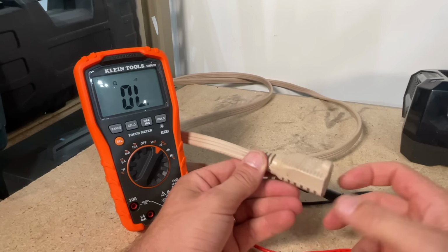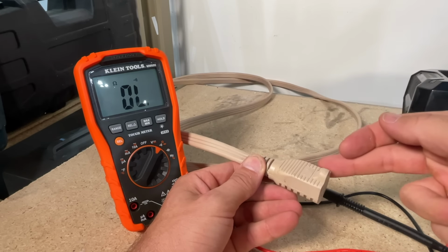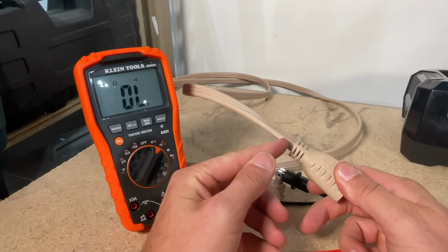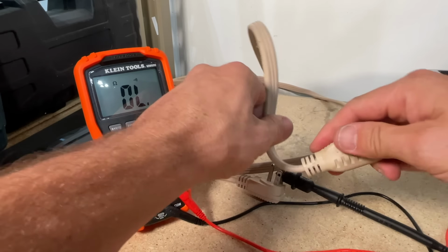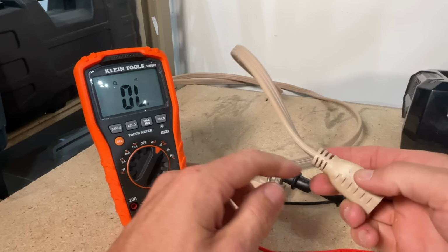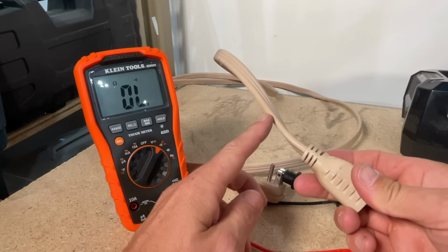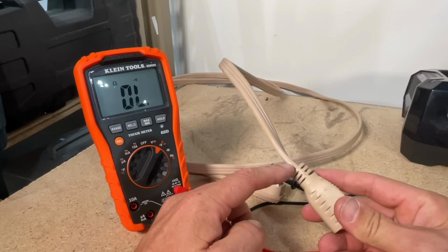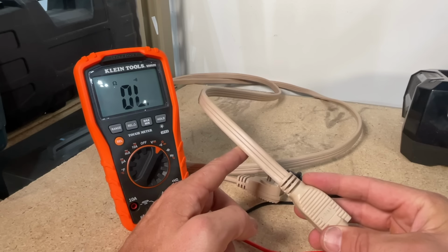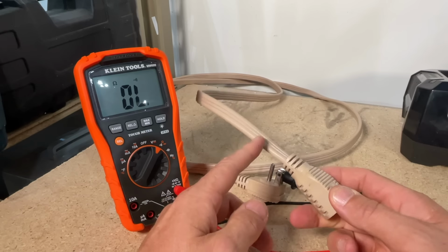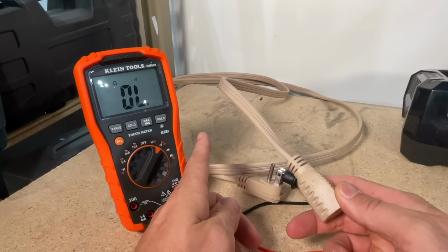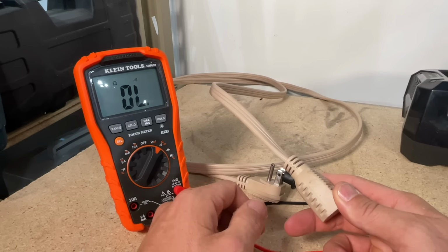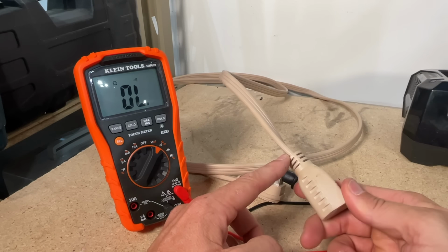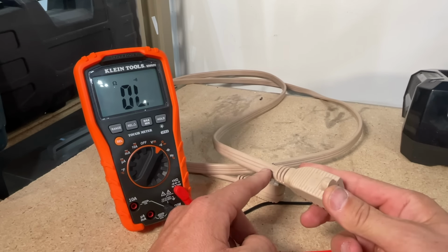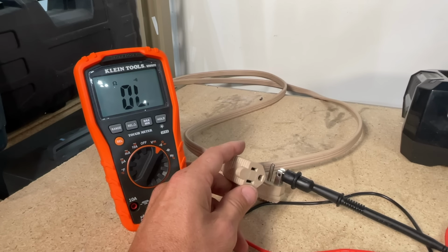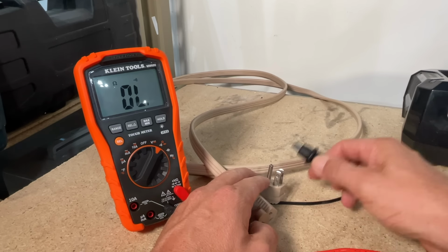So what was I doing? The audible alarm indicates we have continuity all the way through the extension cord. One of the weakest points of an extension cord is where it bends depending on use, which is why there's reinforcement there. If there was an intermittent failure or a weak connection, the wiggle test would produce intermittent on-off sounds from the audible alarm, indicating a failure starting there, sometimes working, sometimes not, meaning it needs to be replaced. So continuity checks and the wiggle test are the most common use cases I use.